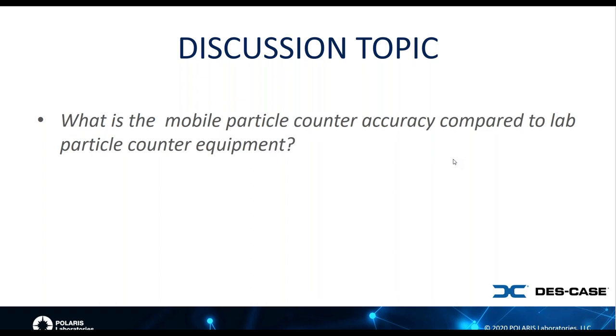Right, and one other thing to keep in mind is that sampling procedures can have a really large impact on particle counting, especially if you're pulling out of a sump and you just pull it straight out of a drain. That can cause higher particle counts than you may be expecting because they've settled out. So make sure you're following the proper procedures for pulling those samples when you send them in, to make sure it's accurate.